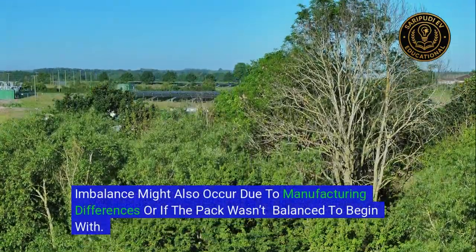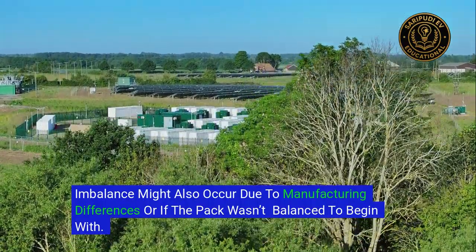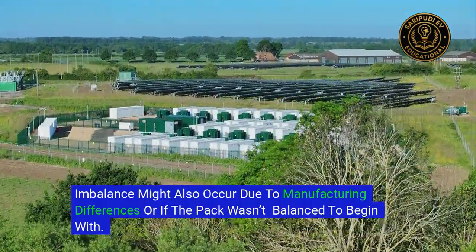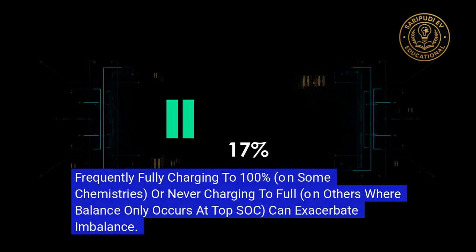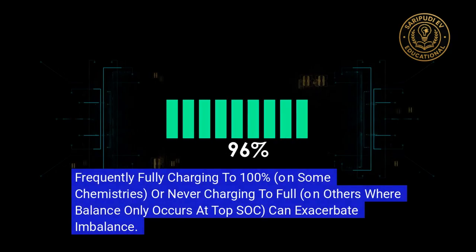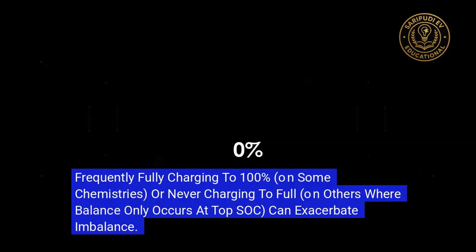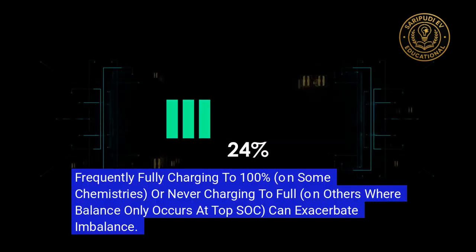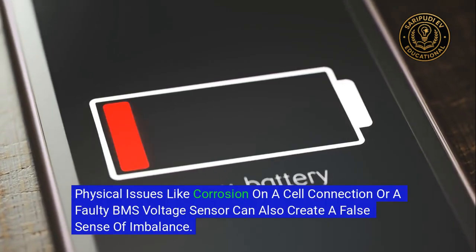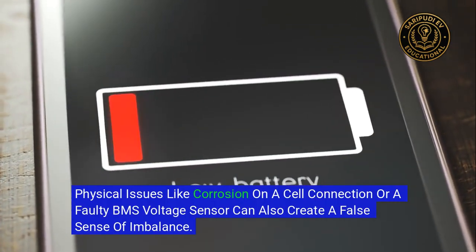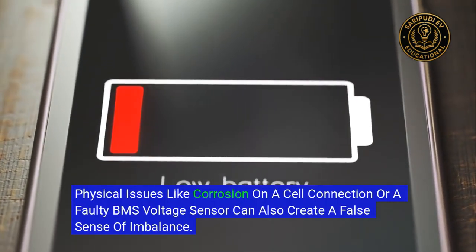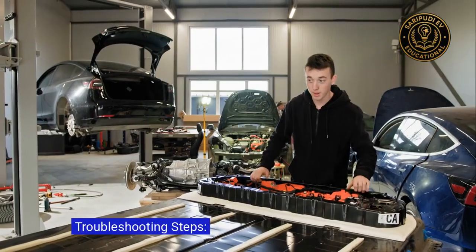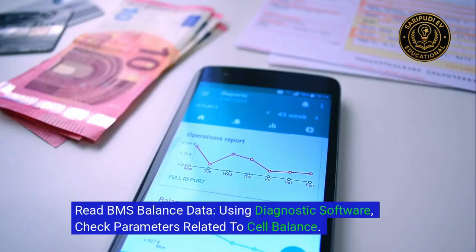Imbalance might also occur due to manufacturing differences or if the pack wasn't balanced to begin with. Frequently fully charging to 100% on some chemistries, or never charging to full on others where balance only occurs at top SOC, can exacerbate imbalance. Physical issues like corrosion on a cell connection or a faulty BMS voltage sensor can also create a false sense of imbalance. Troubleshooting steps: read BMS balance data.